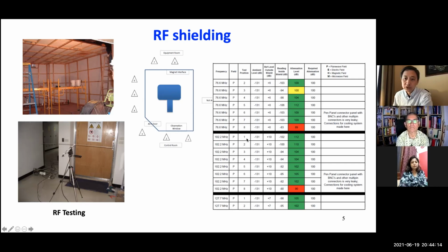And those are different locations. So from 1 to 8, those locations are shown here. And the right-hand side highlighted here is the attenuation. The requirement is 100 dB attenuation. And you can see the yellow highlights just 100, whereas the red is a fail. So it's 89 dB, that's not enough. Okay.